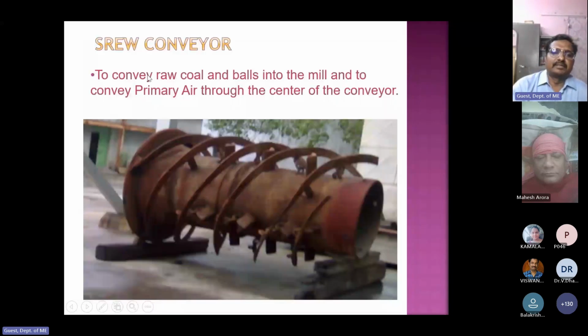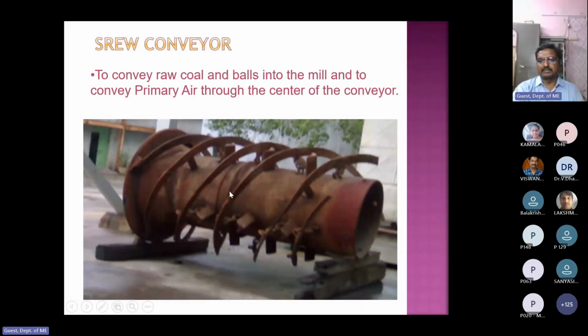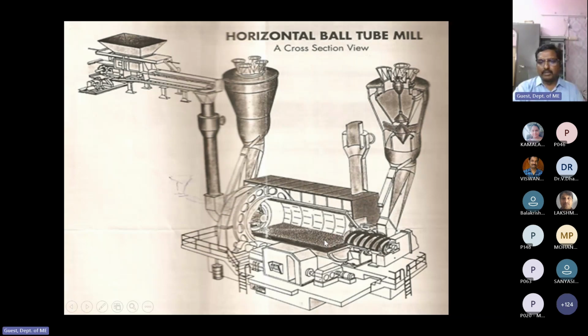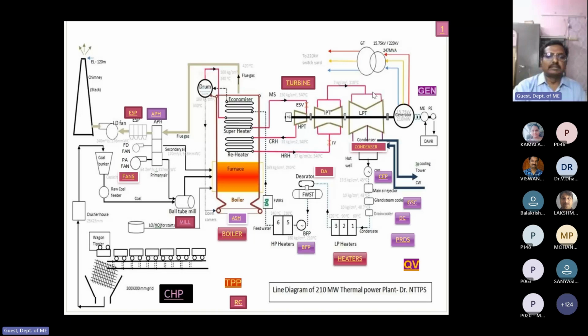This is a screw conveyor which feeds the coal to the ball tube mill. Through this screw conveyor, coal is fed from the outside and air flows from the inside. Through this hollow pipe, air goes inside the mill. That is the primary air, and it takes the fine particles and goes to the furnace directly. This is the overview. In the ball tube mill, coal is fed horizontally from both directions, and when the mill is rotating, it forms fine particles. This fine particle again comes through this area and goes to the furnace directly.